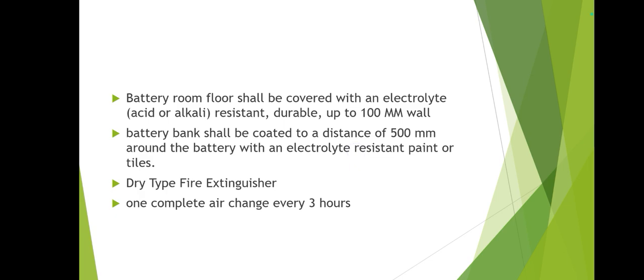The next question is: battery room floor shall be covered with electrolyte, acid, and alkali resistant, durable tiles up to 100mm on the wall. The walls are also covered with the same tiles up to 100mm. Battery banks shall be coated to a distance of 500mm around the battery with electrolyte resistance paint or tiles.